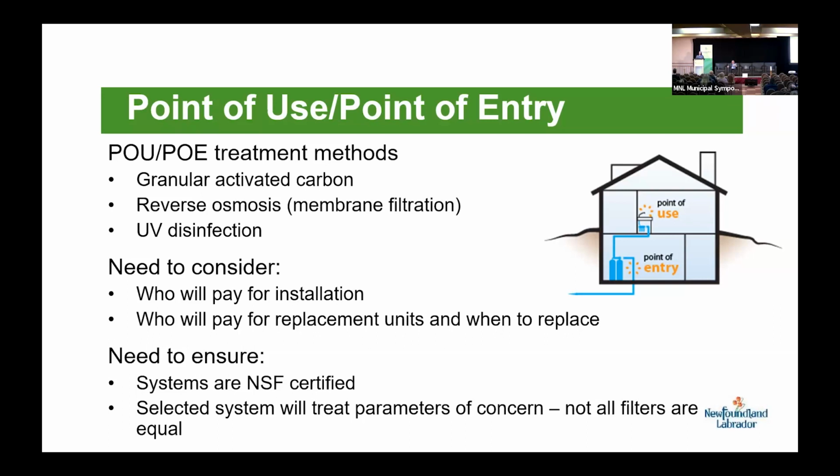Like with any treatment unit, it will have to be maintained. So often with these point of use, point of entries, you swap out cartridges, swap out membrane filters. A couple of things also to consider: the treatment units will have to be NSF certified. That means they're for use with potable water, and they need to be certified for the parameters that you are trying to remove from your drinking water. Not all point of use, point of entry options are going to be equal. So you need to make sure that the one you're choosing is going to address your water quality problems.